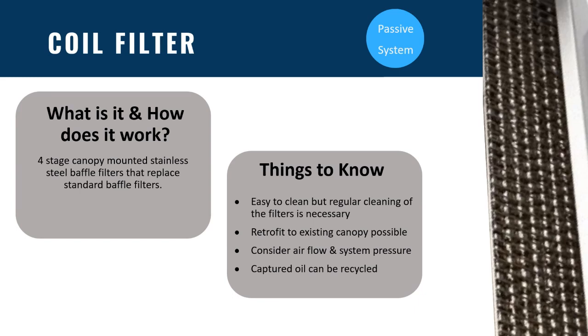Coil filters. What are they and how do they work? Coil filters are canopy mounted stainless steel baffle filters to replace the standard baffle filters. As with traditional baffle filters, they work on extraction air before it gets into the canopy. Their data sheets indicate that they capture 95% of grease particles, which is a huge improvement on the typical 20 to 40% achieved by ordinary baffles.